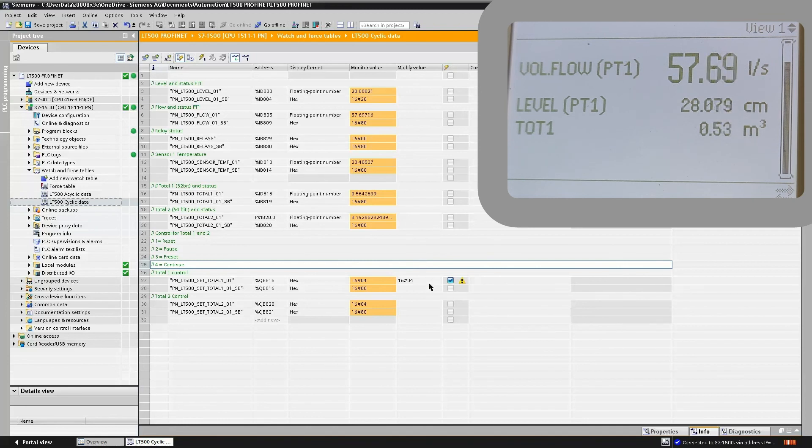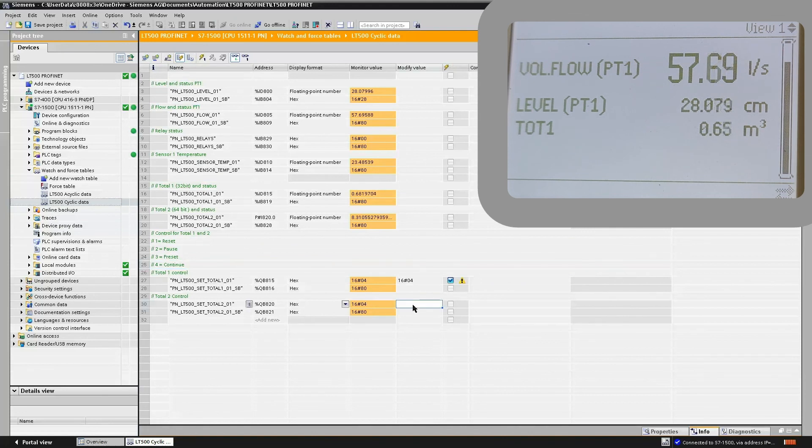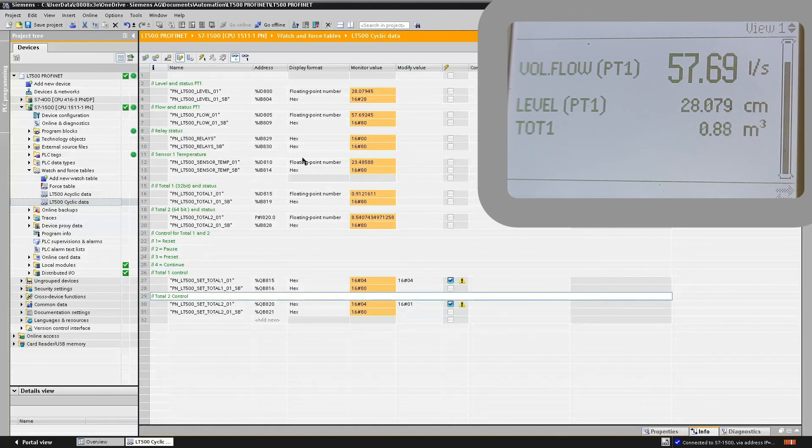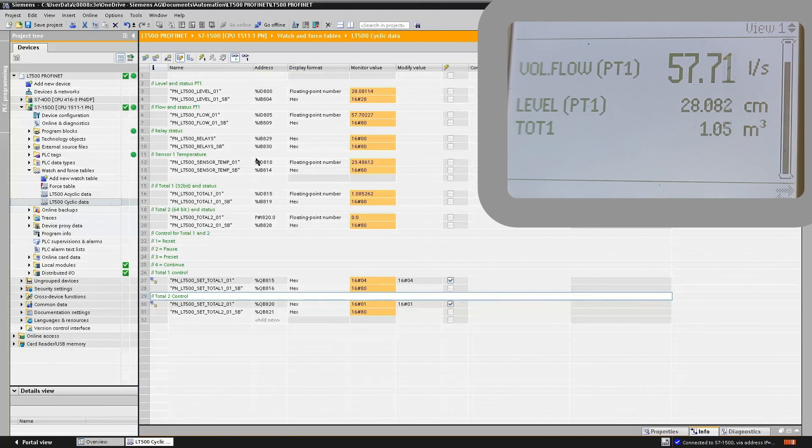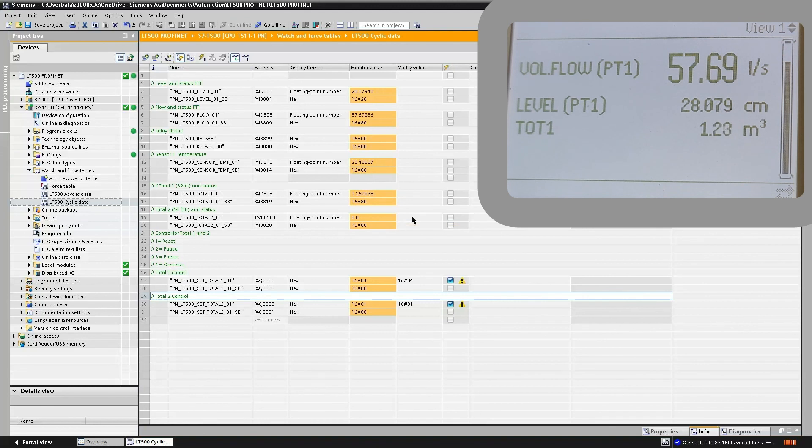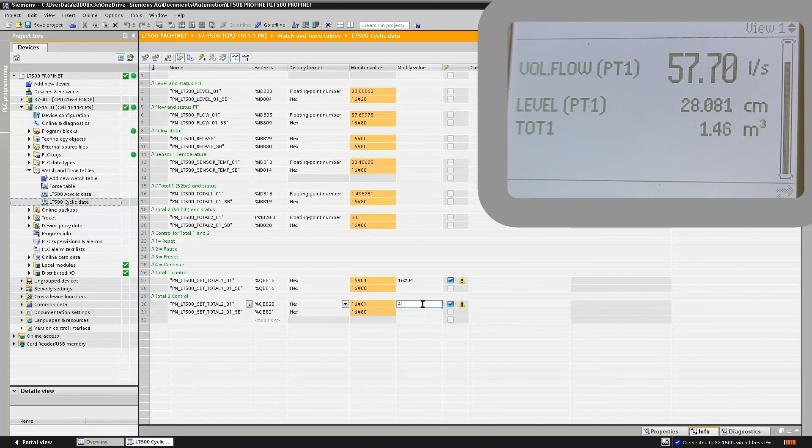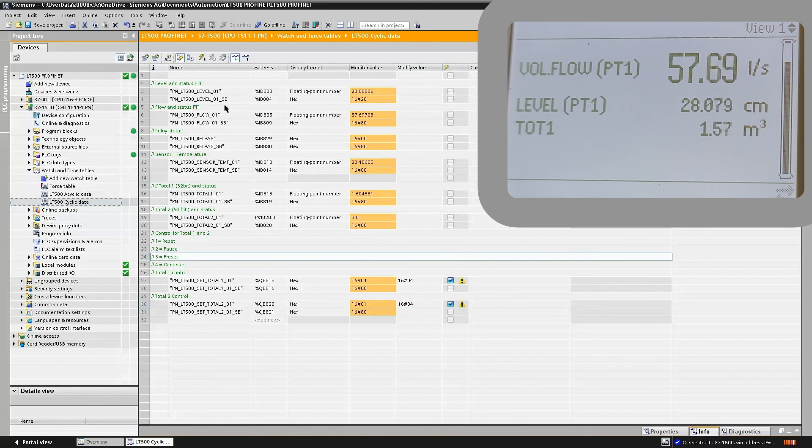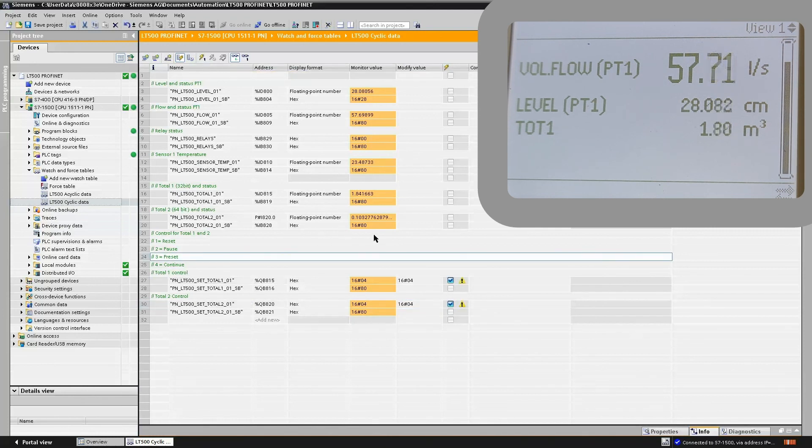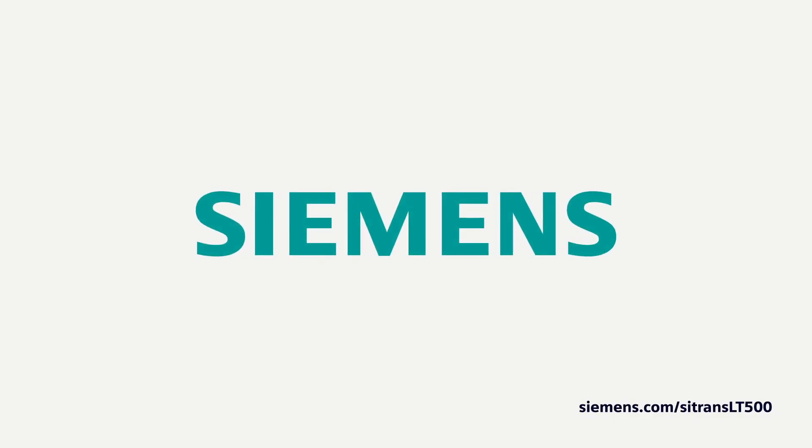Naturally, the same functionality applies to totalizer number 2, in this case, the 64-bit totalizer, which also operates in the same way. If we enter a 1, update our tag list, we see that our totalizer resets to 0. To start the totalizer running again, we enter a 4, update our watch list, and our totalizer will increment once again.